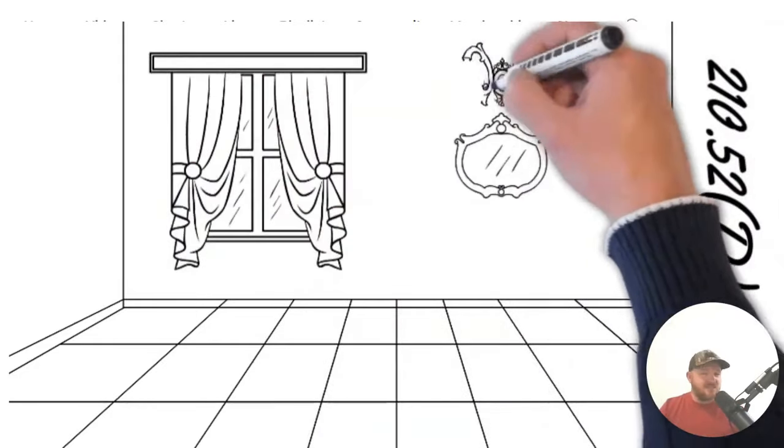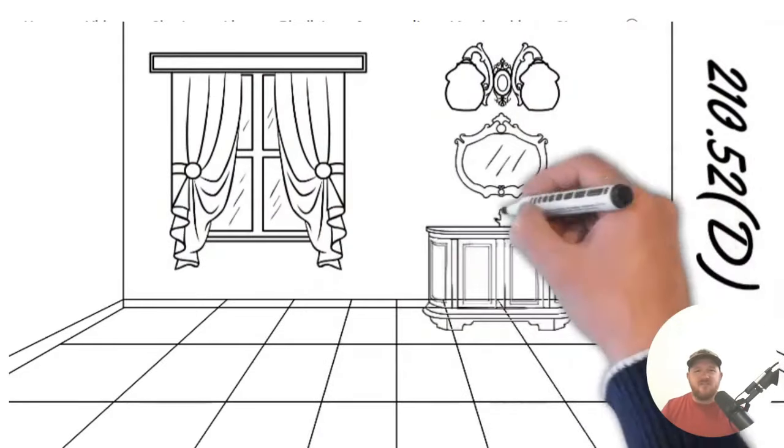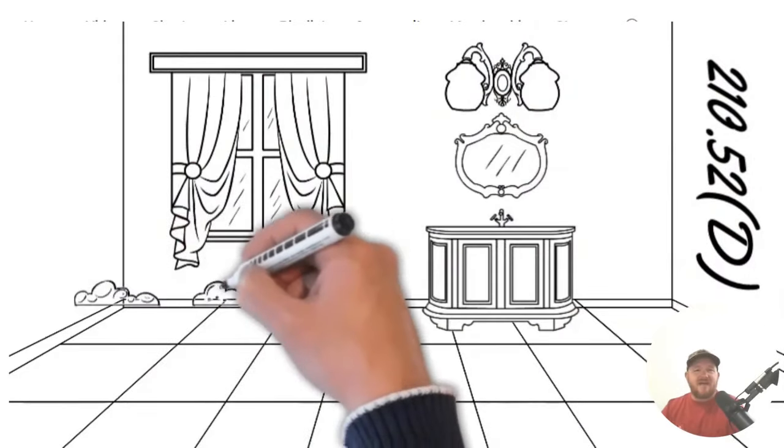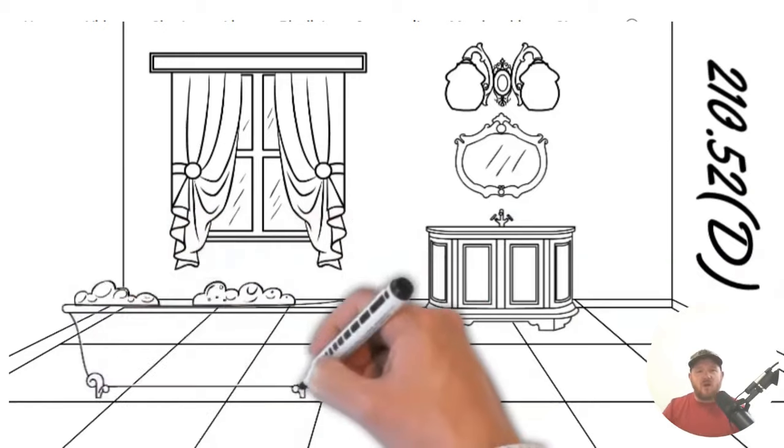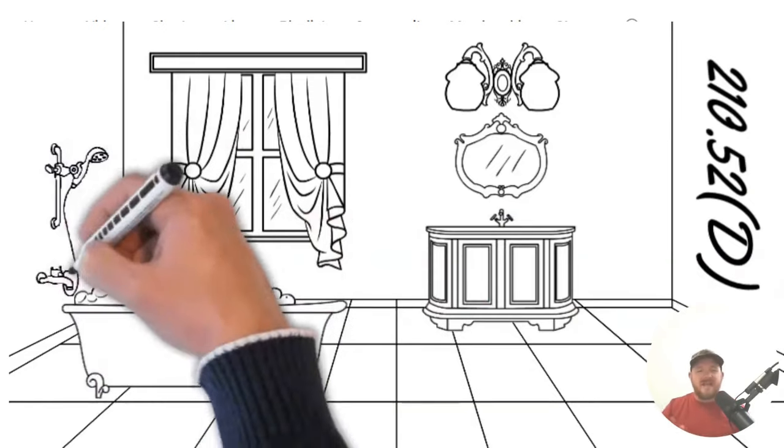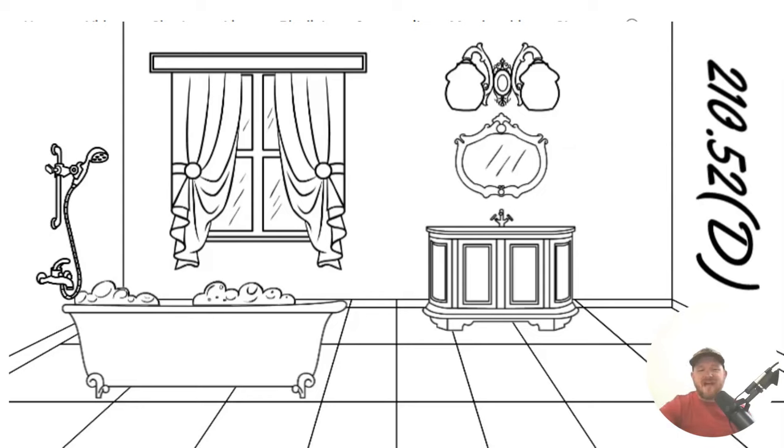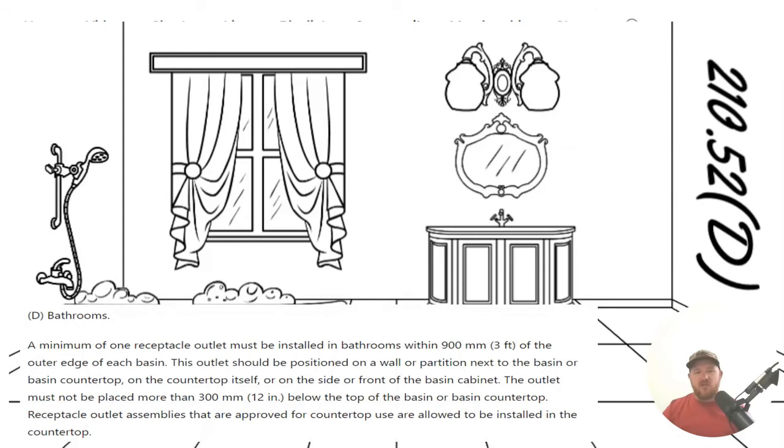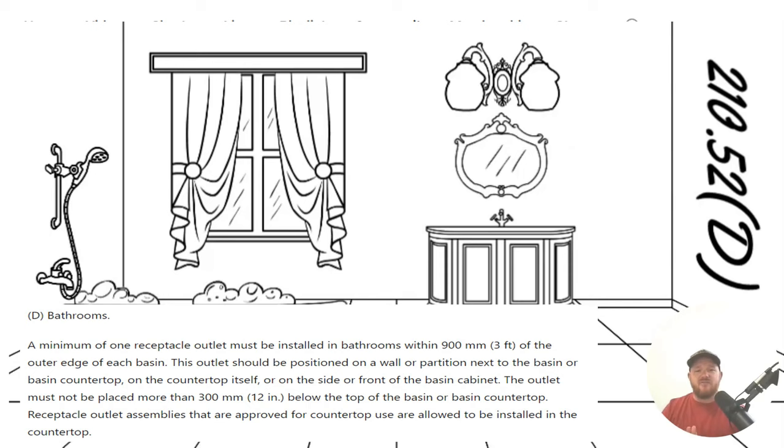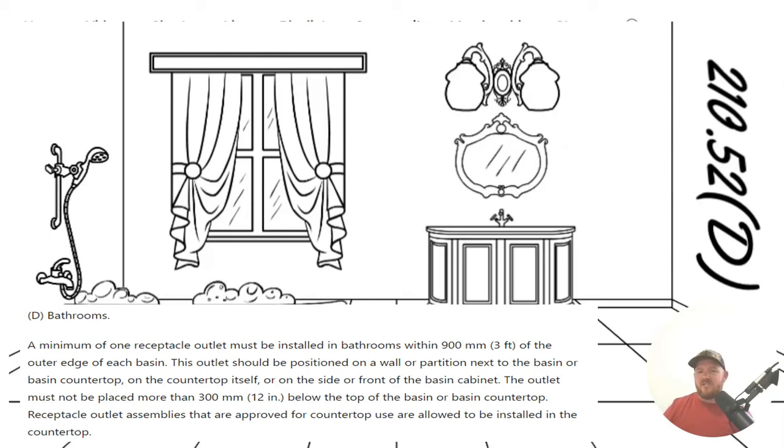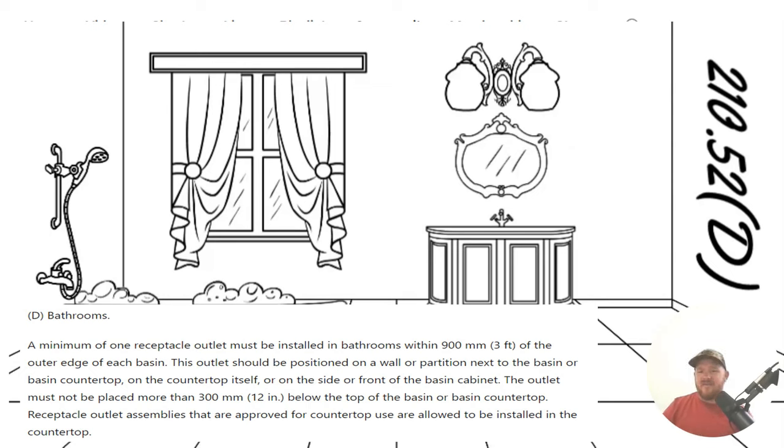Now, when we get to 210.52, that's going to lay out the spacing requirements for almost every receptacle that you can imagine in a dwelling unit. And for this one, let's dive to the paraphrase code language. A minimum of one receptacle outlet must be installed in bathrooms within three feet of the outer edge of each basin. The outlet should be positioned on a wall or partition that is next to the basin or basin countertop or on the countertop itself or on the side or front of the basin cabinet.